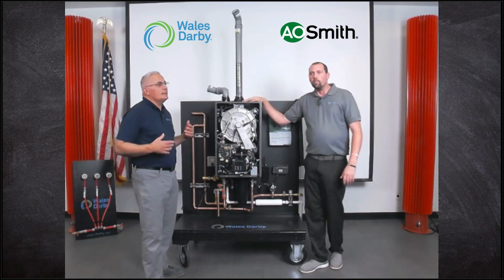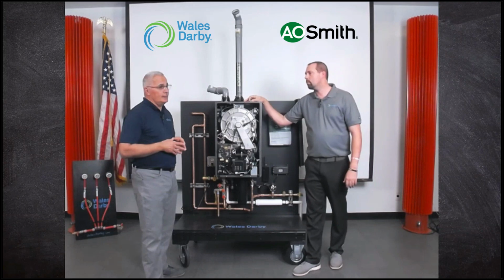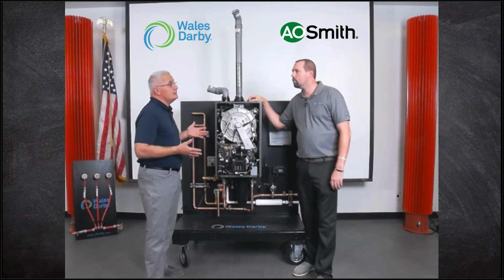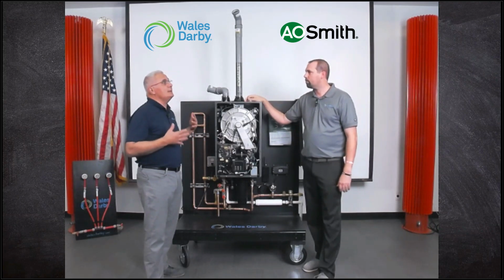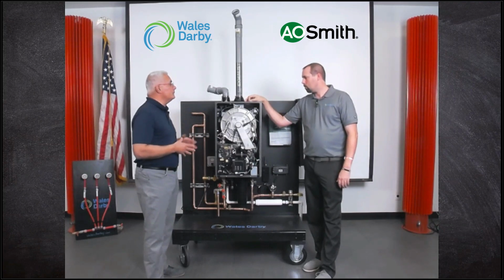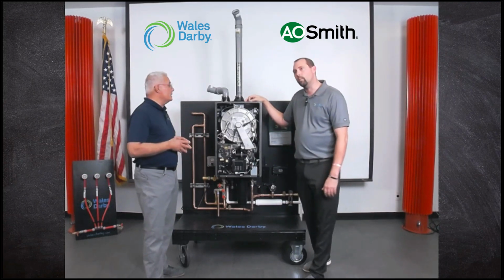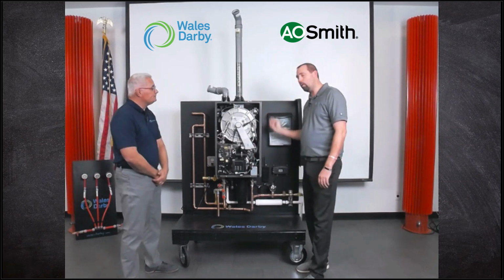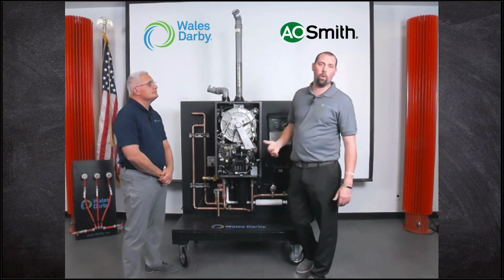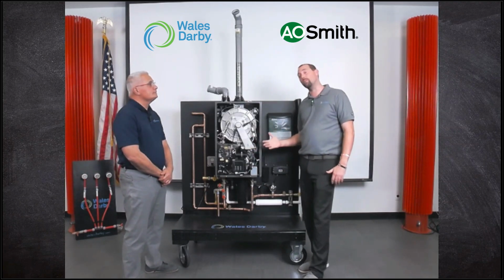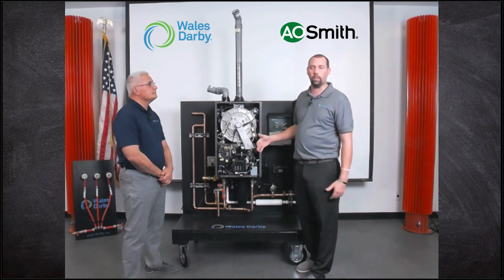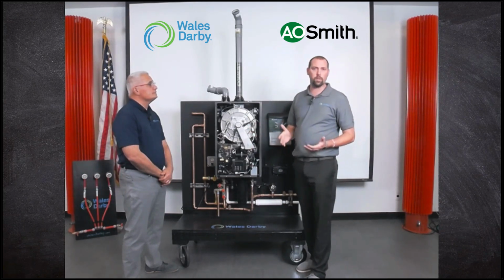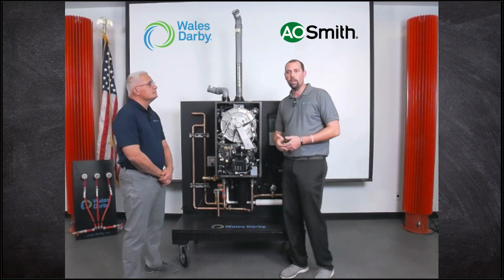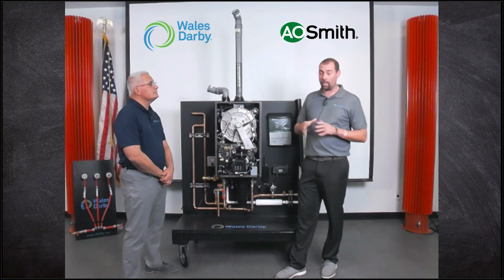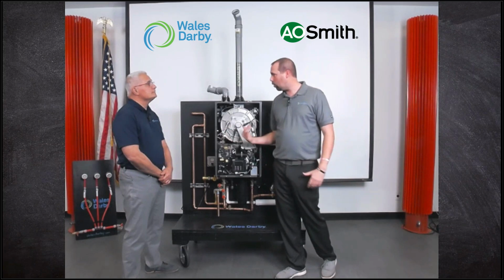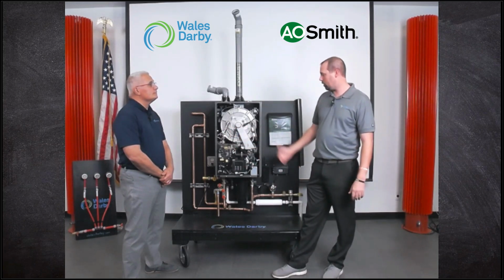We get a lot of contractors looking to put this in to replace tank type equipment. Performance-wise, great: activation is down to 0.4 GPM to activate the unit and about a quarter GPM to keep it running. With the low fire down to 9,000 BTUs and 22 to 1 turn down, we reduce a lot of that cold sandwiching within the system, so you're not going to get cold water coming to you. It's a great unit.